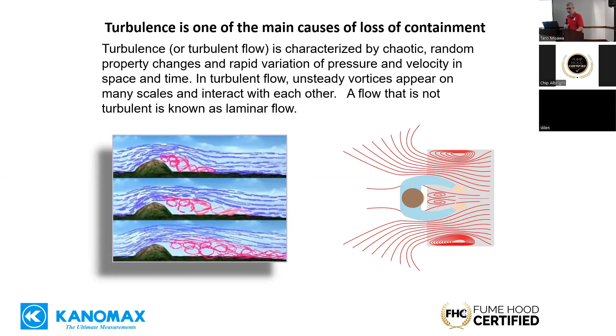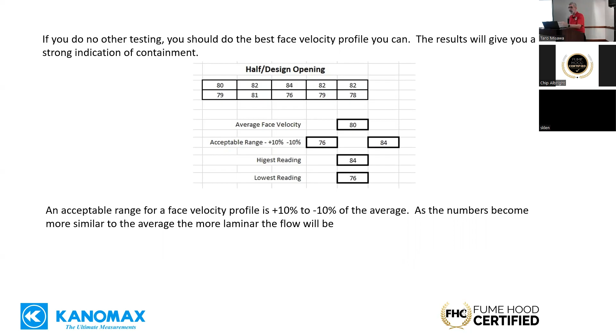So what is the main cause of loss of containment? And it's turbulence. Having been in the industry for so many years, the one thing that we did that was unfortunate is, like in graphics, we show air patterns and they're nice, smooth arrows. Well, there's nothing remotely similar to that really happening. And we'll see that in a couple of the videos. But basically, turbulence causes the rotation, mainly the vortex, to become unstable. And when you have an unstable vortex, then you're going to have loss of containment. So if you're not going to do any other testing, at least do a face velocity profile, because this right here tells a whole lot about how that hood's going to perform.